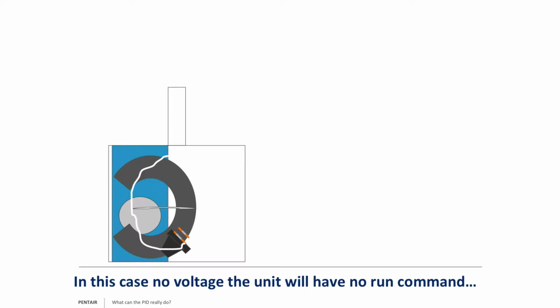Now that takes away the run command. What this is, is a run command. So it sees no run command, it will stop. It doesn't mean it faults. It just means it stops because the drive has no more run command. Okay, so this is one example we can do.